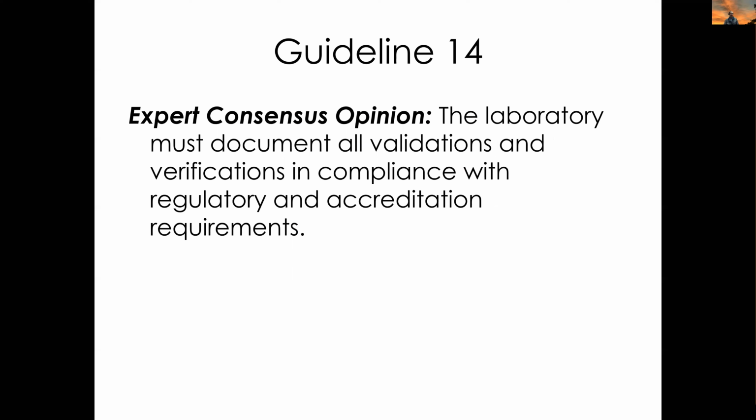So guideline 14: laboratories should document all validations and verifications in compliance with regulatory and accreditation requirements. If you don't have it written down, if you don't have the documentation, it didn't happen. That is the voice of the inspector speaking.